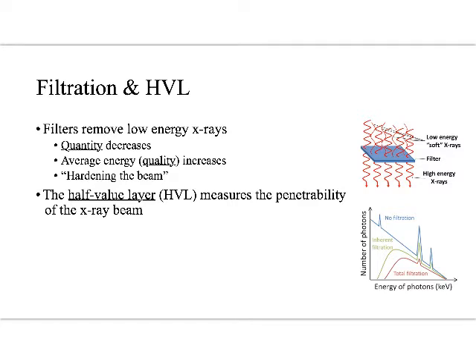The way we measure beam quality is with the half value layer. Looking at the graphic: on the unfiltered side we have both short-wavelength high-energy x-rays and long-wavelength low-energy x-rays. What the filter does is stop the low-energy long-wavelength photon while allowing the high-energy short-wavelength photon to keep on traveling. We didn't lose anything helpful — we just filtered out the stuff that was not helpful, the low-energy x-rays.